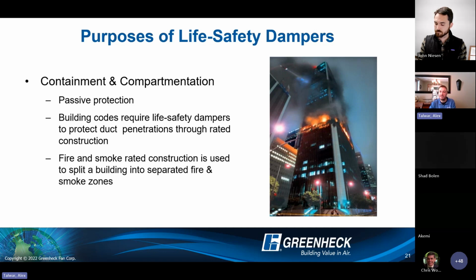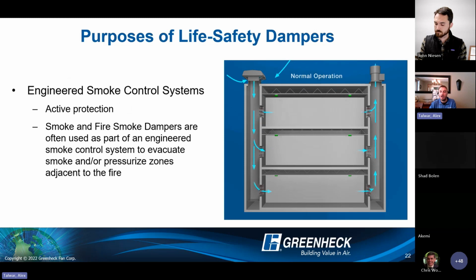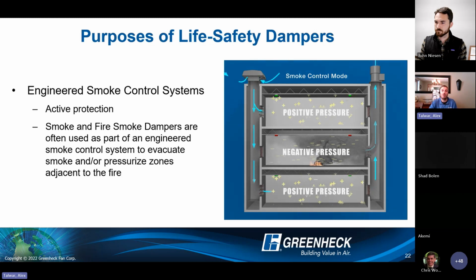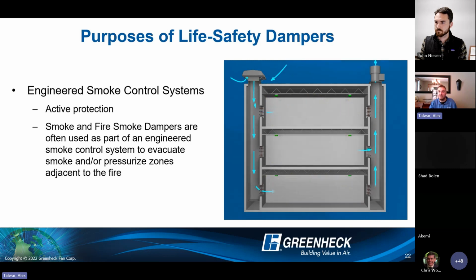So compartmentalization is really the purpose of the International Building Code driven requirements. But we do also see them in more of an active exhaust type of scenario as well, right? These are engineered smoke control systems where if we do sense a fire, we might want more than just to sense flame or smoke and close the damper, right? You might want to actively exhaust that smoke out of an area, and prevent cross-contamination in other areas. So it's a very simple example here of a smoke control system. But this is something that would fall a little bit more outside of the International Building Code requirements and go a little bit deeper into the individual smoke control systems themselves.